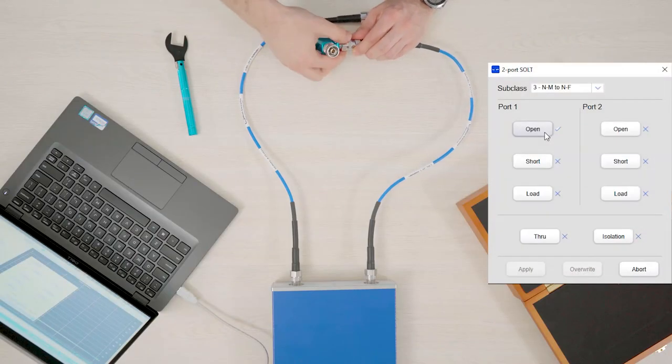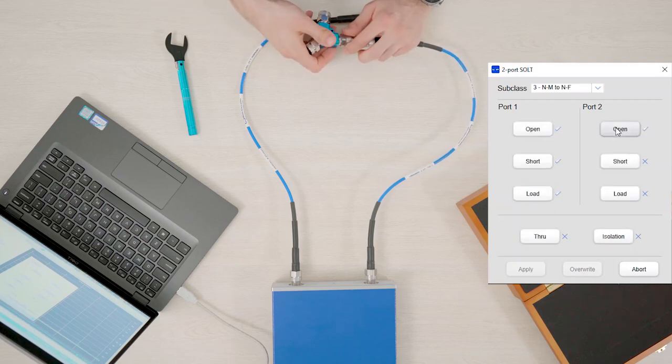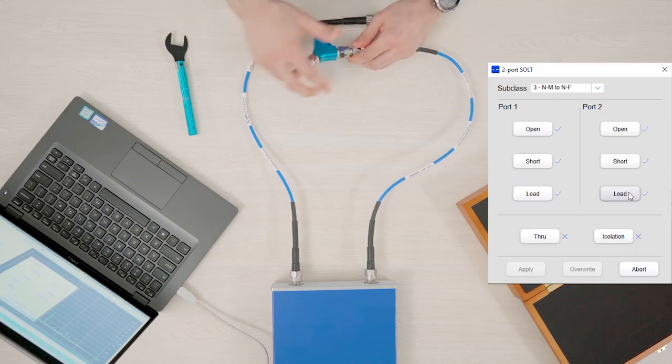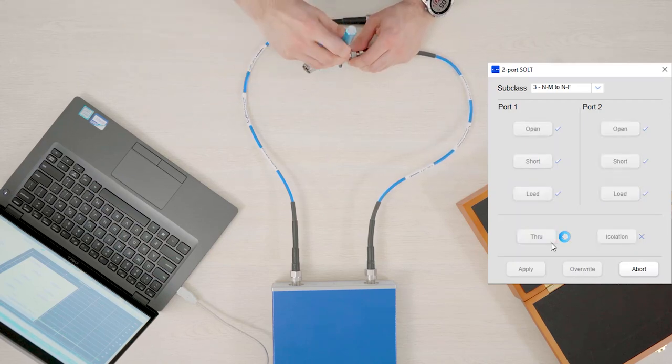One by one, connect the appropriate calibration standard to the measurement ports of the EVNA and click the corresponding button to make the measurement. We do this for the open, short, and load on both ports, as well as a through measurement.